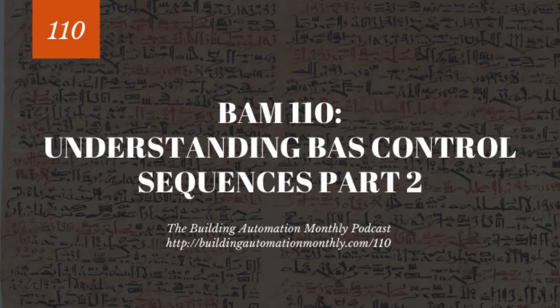All right, so as I said, there are occupied mode set points and unoccupied mode. And what happens with this sequence is when the zone temperature is greater than its cooling set point, okay? Oftentimes you'll have a set point, say a space set point of 72. And then you'll have this concept called deadband.